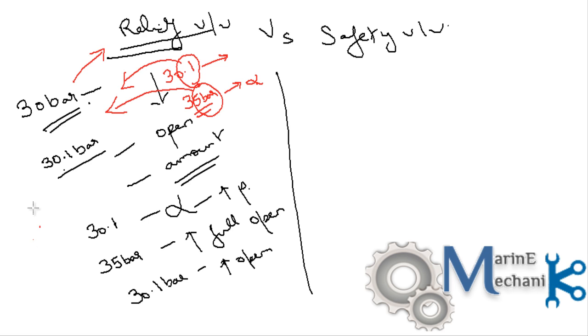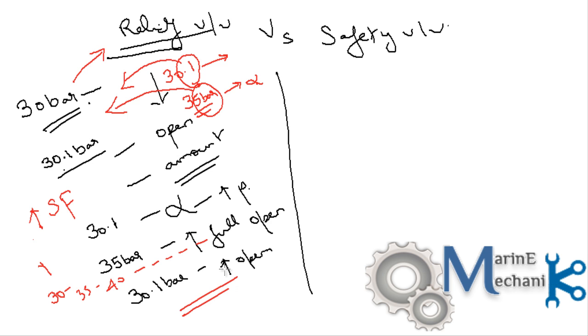The relief valve is an ordinary spring loaded valve. As you adjust the spring tension, the pressure at which the relief valve opens increases. Tightening the spring raises the opening pressure from 30 bar to 35, 40, etc. — you can adjust within the operating design range from lower to higher. Importantly, when a relief valve opens, it does not create any immediate emergency or immediate need to attend the air compressor or pump, so operation of a relief valve does not require immediate attention compared to the safety valve.